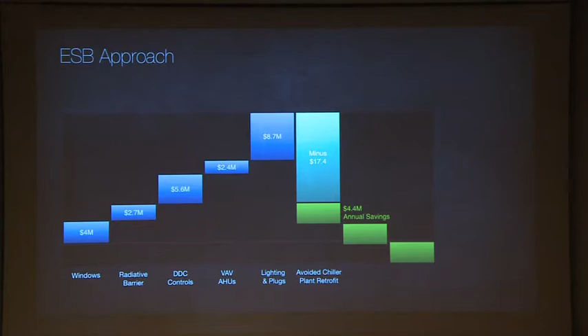Remanufacturing its 6,500 windows on site into super windows that pass light but block heat, plus better lights and office equipment and such, cut the maximum cooling load by 1/3. Then renovating smaller chillers instead of adding bigger ones saved $17 million of capital cost, helping to pay for the other improvements and cutting the payback to just 3 years.